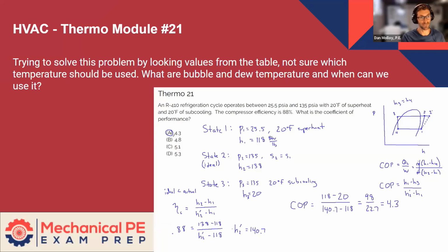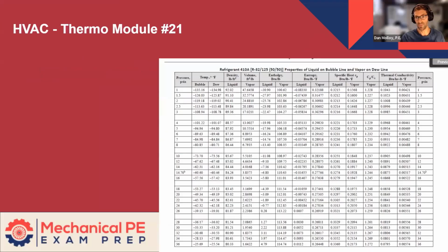But anytime you start mixing refrigerants together to make something else, you have the potential that you're going to end up with a zeotropic refrigerant. And that's the case with R410, because it's a 50-50 mix of two different refrigerants, R32 and R125, which have different properties and therefore different boiling points. But fortunately for us, when dealing with R410, the boiling point is nearly constant. It's not constant, but it's nearly constant. And that's why you'll see that these values are very close. They're off by, maybe a couple tenths or less.